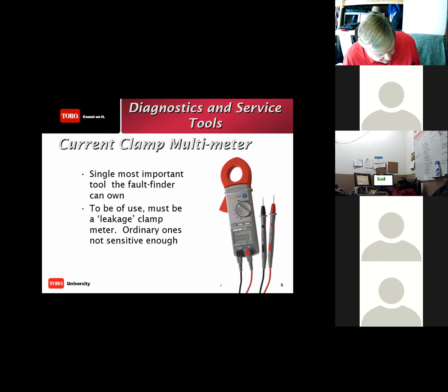Now it's a specific one. On the meter itself, if you can see real closely in this photograph, it says down here underneath the display, leakage current tester. This clamp meter is specifically designed for 2-wire low current readings. Your average clamp meter will not work on 2-wire. They are not able to read, fine tune, the current that we typically use on 2-wire.